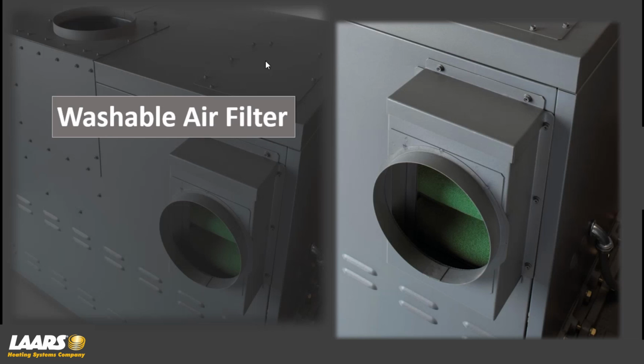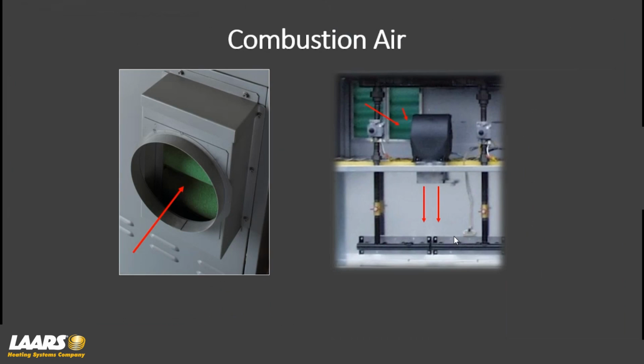So combustion air, again, you can put this filter box up on top. There is a plate up here. Remove the plate, put the filter box up, and then put the plate on the back side. So we filter the air, and we also have a collar here for ducting. You can duct your combustion air to the outside. So combustion air comes through the filter into the blower down into the plenum area for combustion air. These are also considered a positive gas train. What that is, anytime a gas valve's energized, whatever you set your manifold pressure to, every time that valve's energized, that's what it's delivering. So each gas valve would be set up, in this example, at 2.5 inches of water column. What's left is your combustion air, and that's why you would have an air shutter adjusting your CO2s.